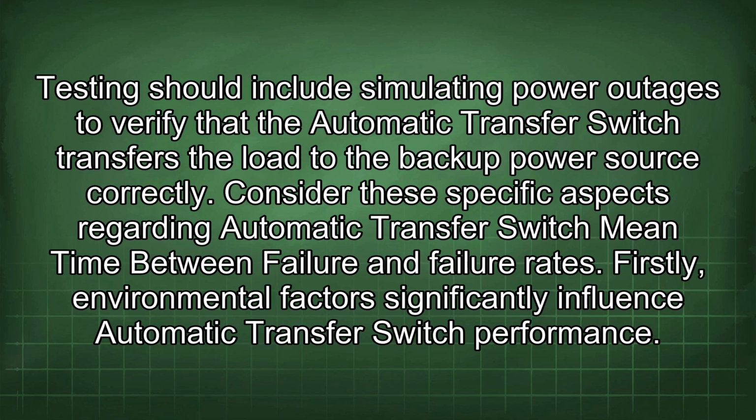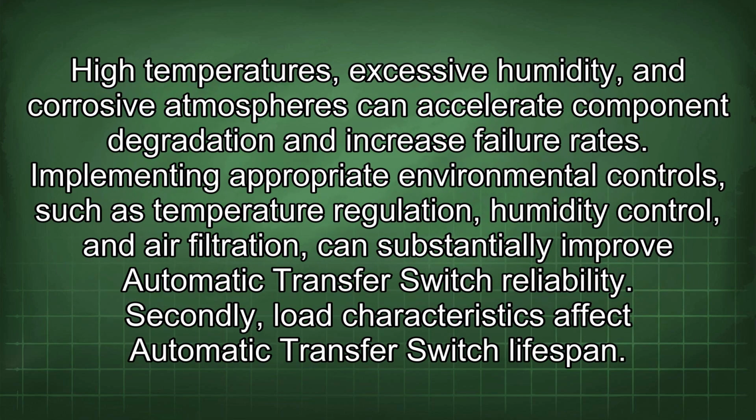Firstly, environmental factors significantly influence automatic transfer switch performance. High temperatures, excessive humidity, and corrosive atmospheres can accelerate component degradation and increase failure rates. Implementing appropriate environmental controls such as temperature regulation, humidity control, and air filtration can substantially improve automatic transfer switch reliability.